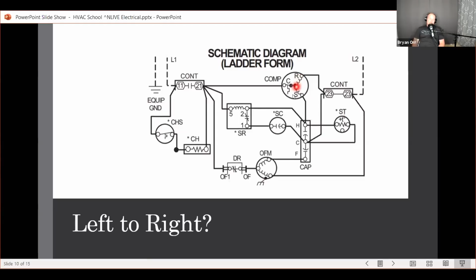Now, why doesn't the compressor start running? Why doesn't it overheat? It's because this crankcase heater has a significant resistance. So the answer is this run winding is actually going to warm up, and that becomes part of the crankcase heater strategy. It's not enough current to run the compressor, but it is enough to have a warm run winding, because if you've ever measured the resistance on a compressor winding to winding, and this is one of my biggest pet peeves I see people do, is they will measure.